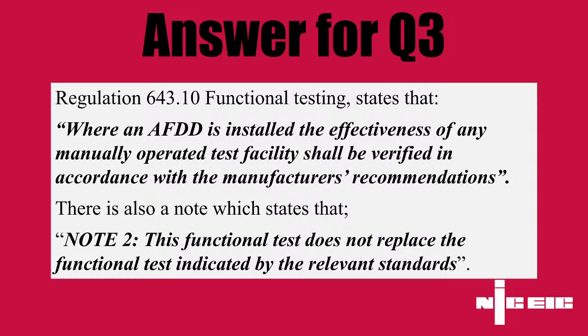And as I say, often you'll find AFDDs built in with RCCBs or RCBOs, and they often have a test facility on there that does have to be tested, where that manual test facility has been provided. So there's no other testing that's required in the regs, but you have got that reference to functional testing, where the AFDD does have that manual test facility. Yeah, absolutely. And the devices themselves have got integral test functionality, so they effectively run periodically themselves and on startup, but there's not always a manual test button available.